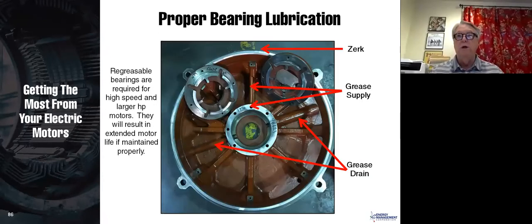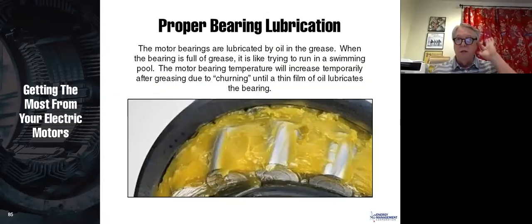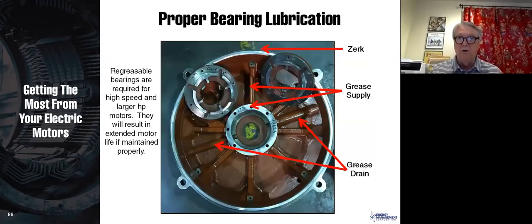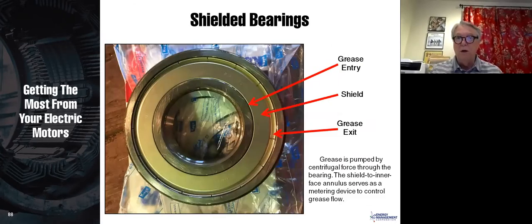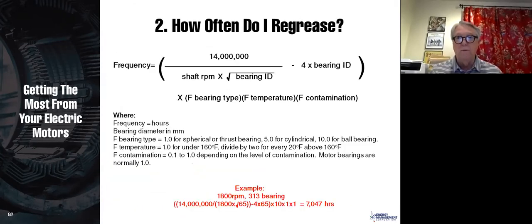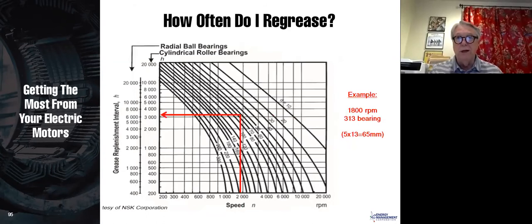and then spent a fair amount of time talking about how to lubricate. We mentioned this is a good lubrication job, but you certainly wouldn't want your motor to run this way. It would be like trying to run in a swimming pool. And so that's great to have that amount of grease in there. Remember, the grease is not the thing that lubricates the bearing. The oil in the grease lubricates the bearing. The grease is just there to hold the oil in. And so you need to leave your drain plug out, run that motor for about 30 minutes to allow it to pump that excess grease out. Otherwise, your bearing will run hot.